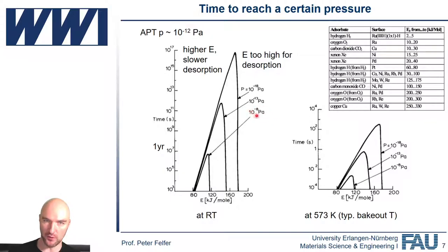And you can see at the pressures we are working at, 10 to the minus 8 pascals, it's about 10 to the 7 seconds, or about a year. So you can go to those pressures, but it will take very, very long. And we have some colleagues that rarely bake the systems because they have a bunch of different systems. When they open one, it's fine. They close it up, they wait for a couple of weeks, and then the pressure is where they kind of want it to be.